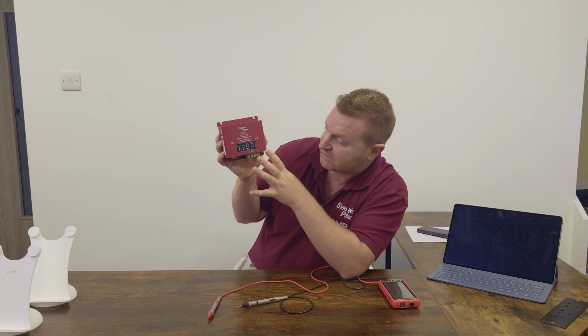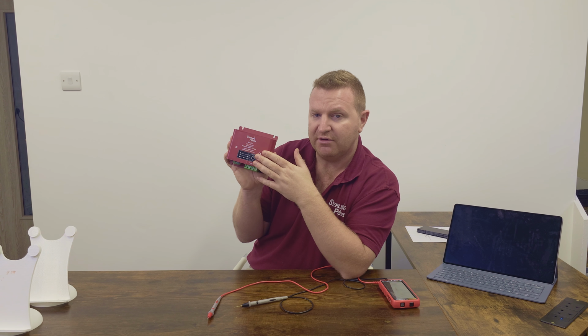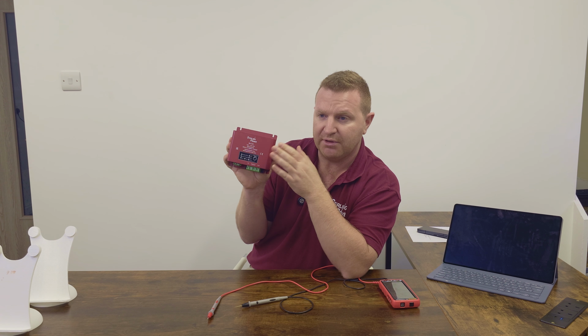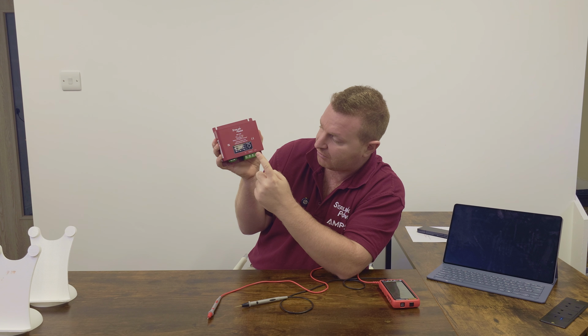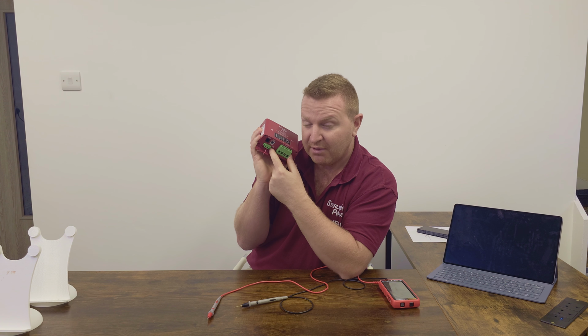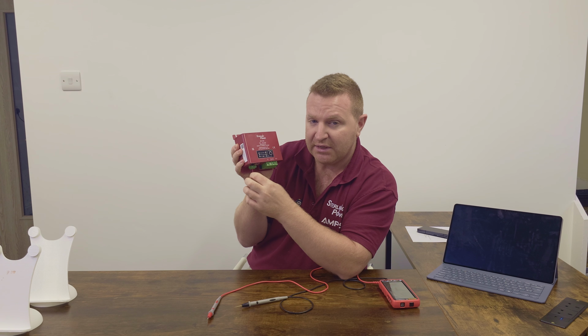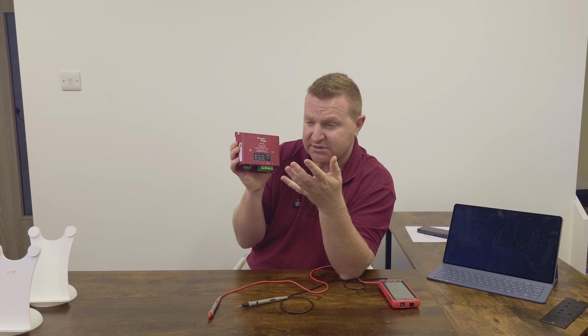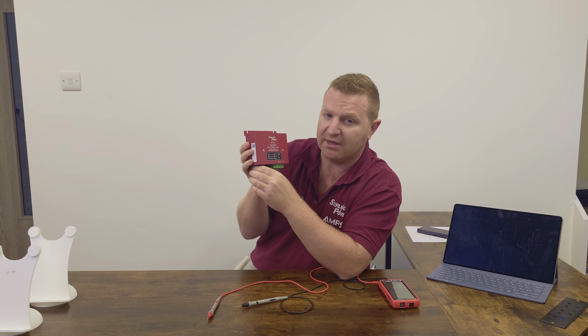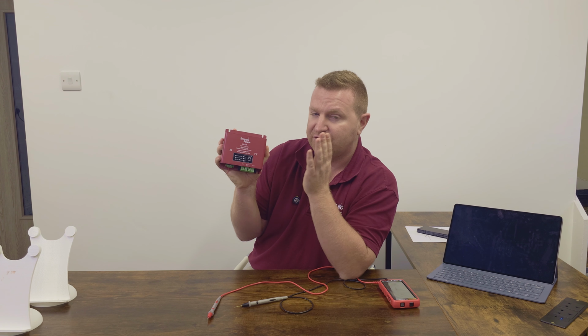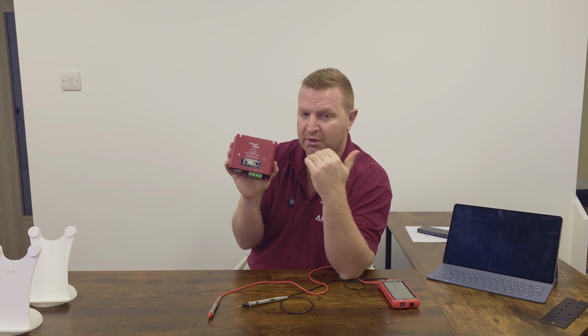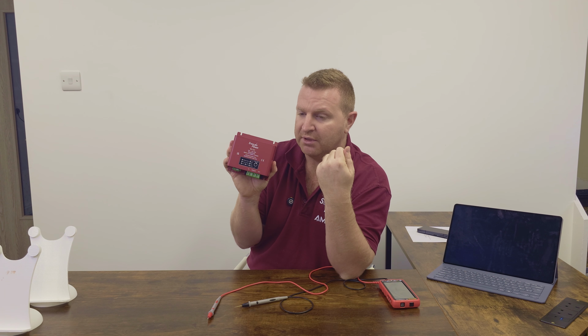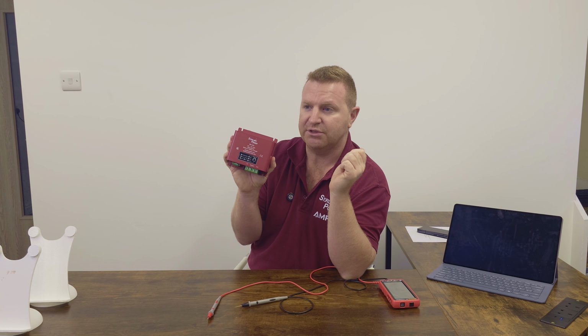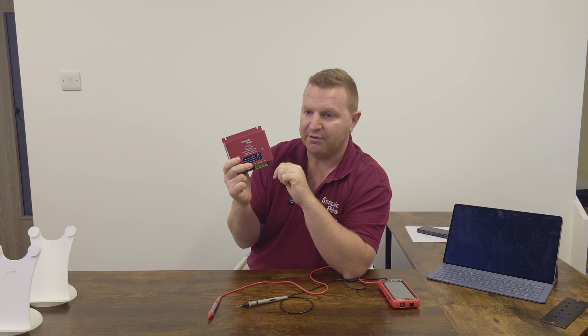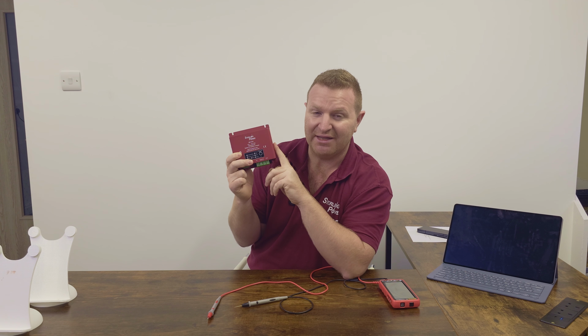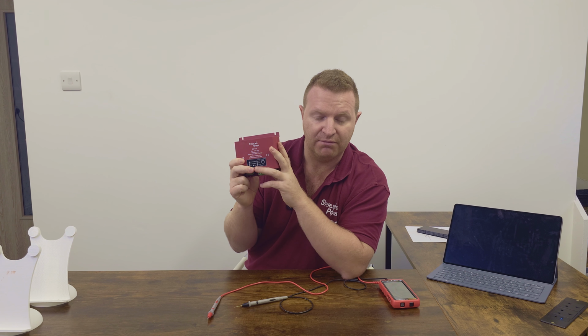So that's the main things with the DC-DC charger, with the Saturn range of B2Bs. To recap: voltage in, voltage out, vibration sense—make sure that's in the off position. And if you need it, I'd say 60–70% of installs, I would always recommend installing an ignition feed. It allows the unit to operate with an ignition or engine signal, and to switch off when you kill the ignition. It's a very binary and automatic way of getting this thing to operate—it cuts through all the nonsense.